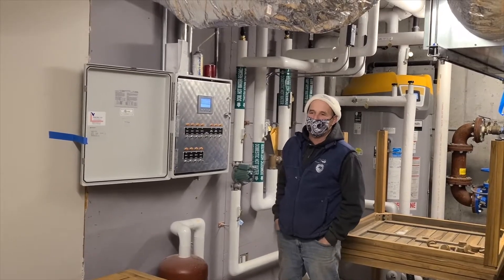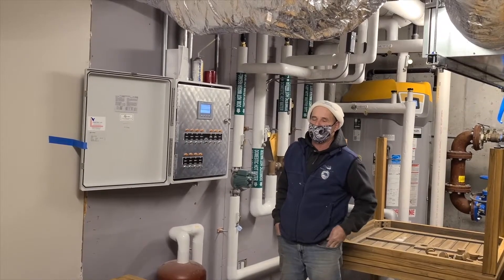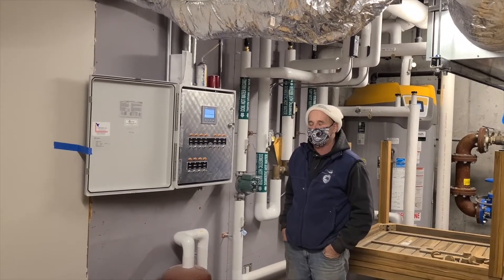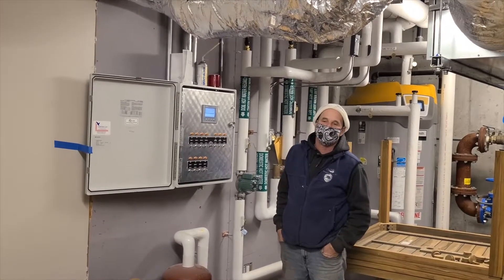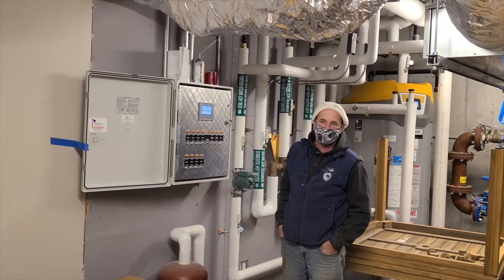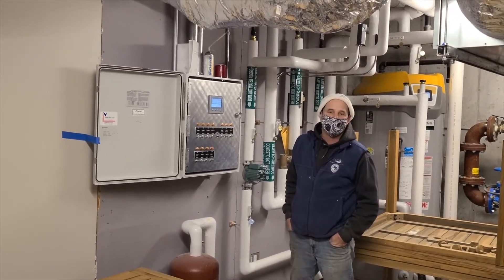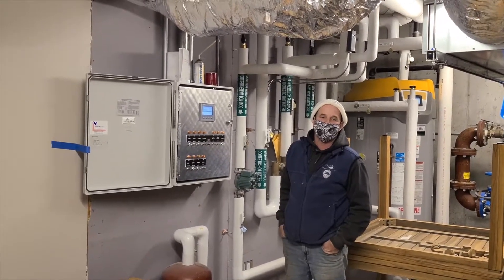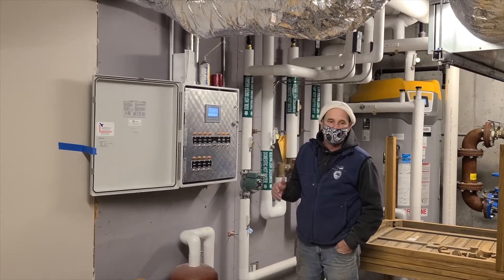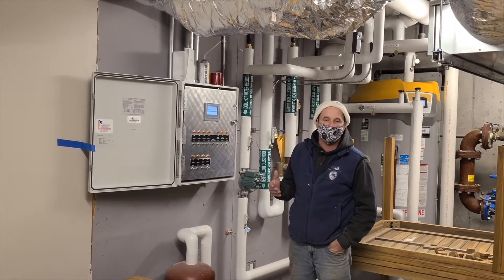This system here, which has a full year-round restaurant, consists of two 2,500-gallon in-series grease traps that are outside, which then flows into a 12,000-gallon septic tank, which then flows into an 8,000-gallon settling tank, then to the 6,000-gallon pump chamber, which is part of this Perc-Rite system here. The system does not have pre-treatment, so it is taking care of straight effluent.